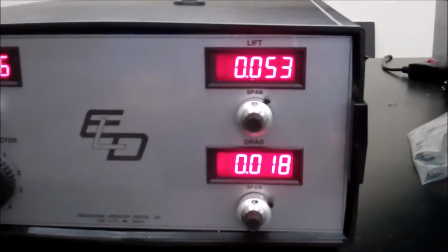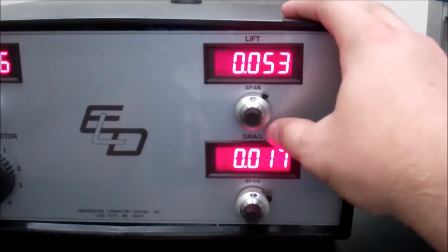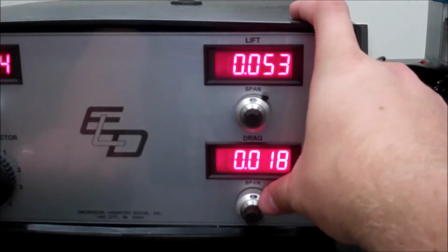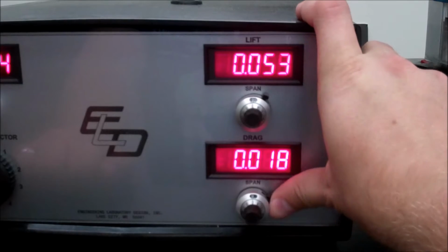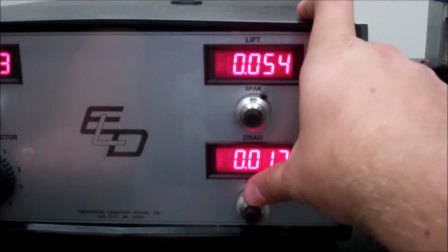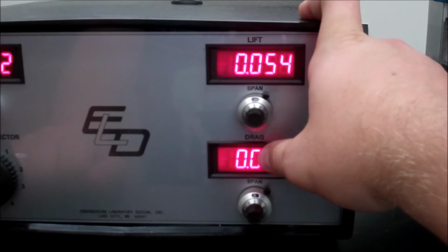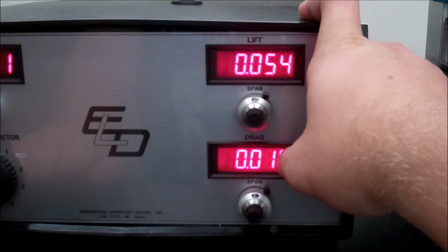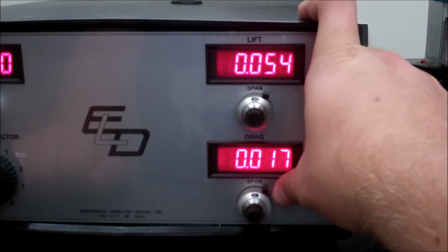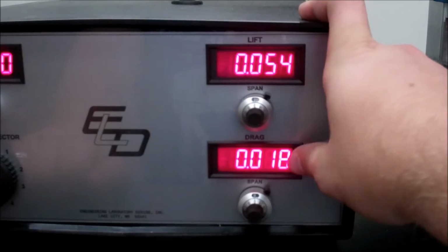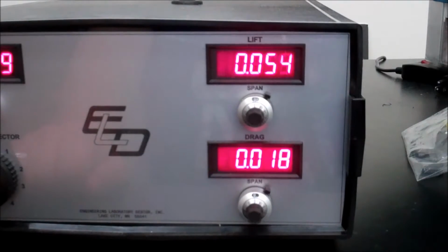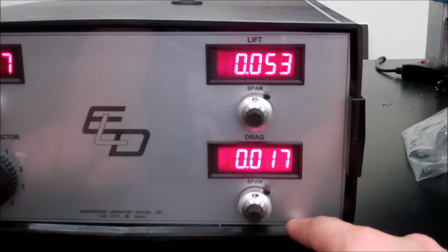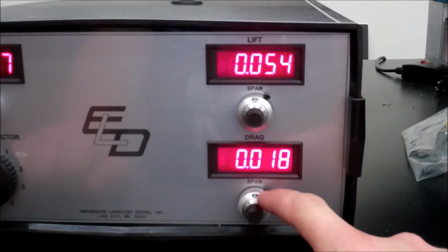Now, on the right here, you can see it says lift and drag, and you notice this little span dial. It determines the amplification, so it amplifies the voltage output of the force balance itself. You're going to want to set that to what you want before you calibrate. You're calibrating based on the voltage being displayed. So if you're trying to find a smaller change, you're going to want to have this at a higher amplification.